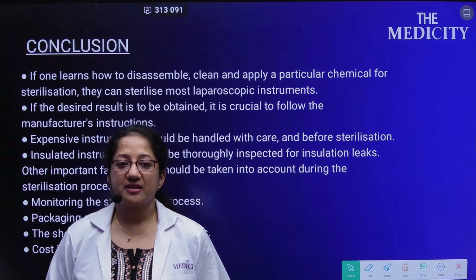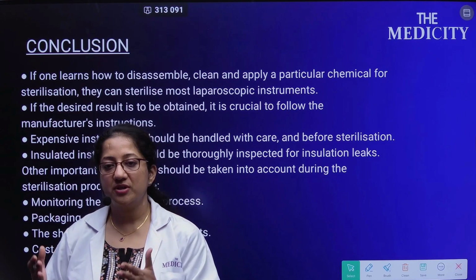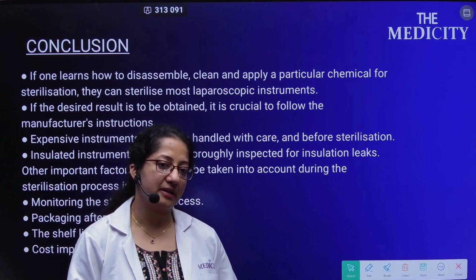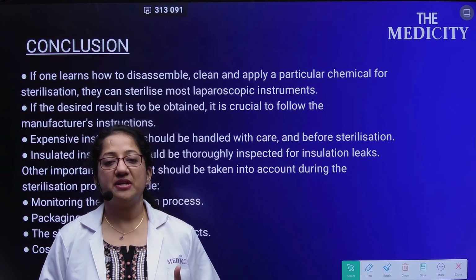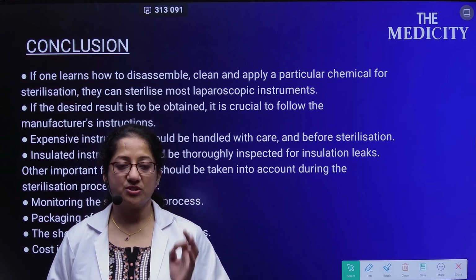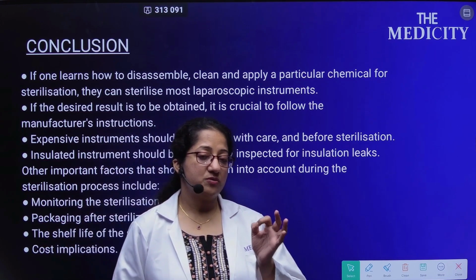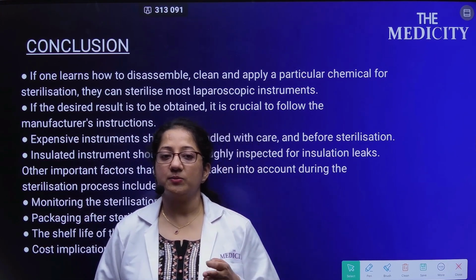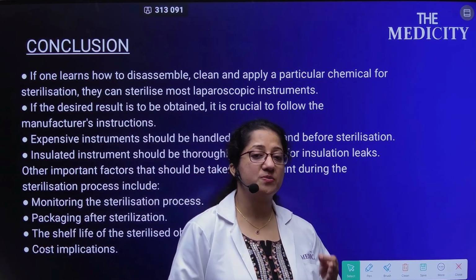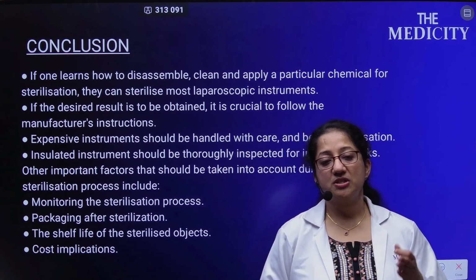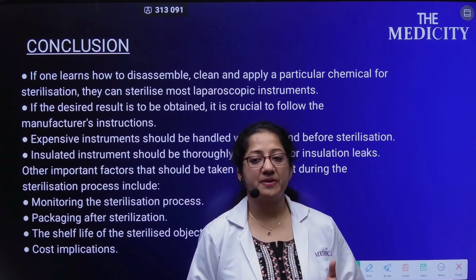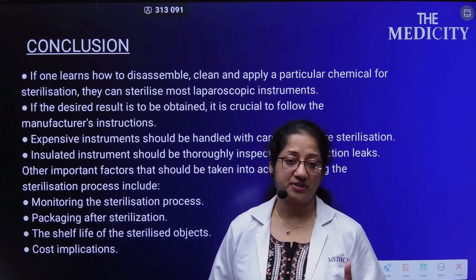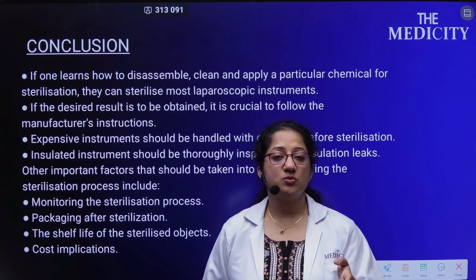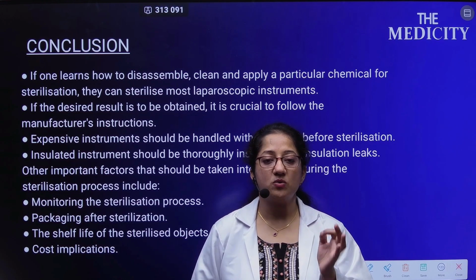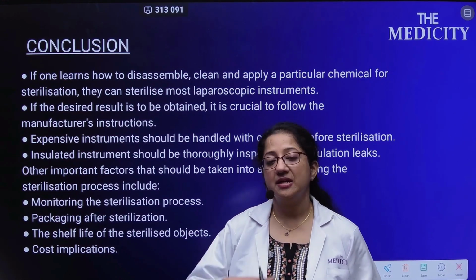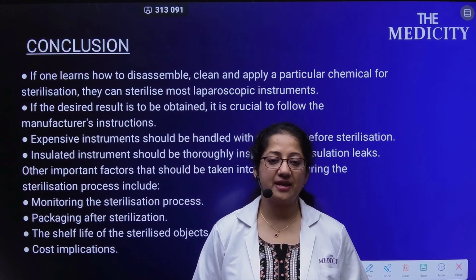The sterilized instruments need to be stored properly so that they don't get contaminated again. If the desired results are to be obtained, it is crucial to follow the manufacturer's instructions. If there is any doubt, it is always better to call somebody and take help. Expensive instruments should be handled with care before sterilization. Insulated instruments should be thoroughly inspected for any insulation leaks, especially the cautery. If the bipolar or the monopolar we use has a leak, it can lead to serious bowel injuries which may go undetected. And in the post-operative period, the patient can have a lot of problems.